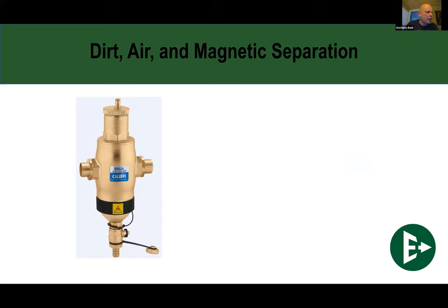So now we have a couple different pieces. We have the two-in-ones. This is dirt, air, and magnetic separation all built into one. Common question for this one: where does it go in the system? Air is the most important thing to get out of a system. Without air, it's harder for dirt to form, and harder for magnetite to form. So make sure that air is your primary concern. You put this at the start of the system, where the water is the hottest and the pressure is the lowest. Get that air out and have it be the first line of defense in the system.